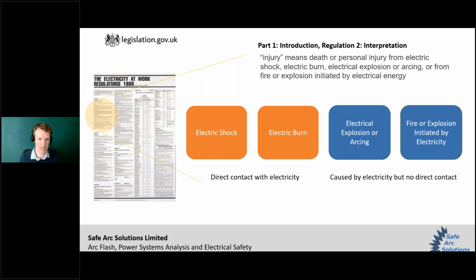On the other end of the scale, we've got fire or explosion initiated by electricity, and this is really where you've got a spark lighting a gas cloud and causing a major accident hazard. So we have things like DSEAR and PFEER, and the use of appropriate equipment in explosive atmospheres to deal with that one. That really leaves the fourth one, which is electrical explosion or arcing, and that's really what we're discussing today in this webinar.